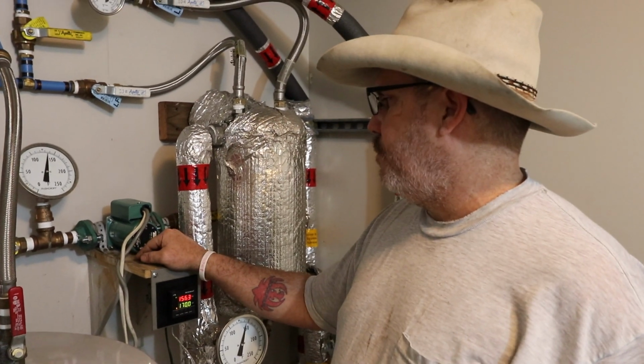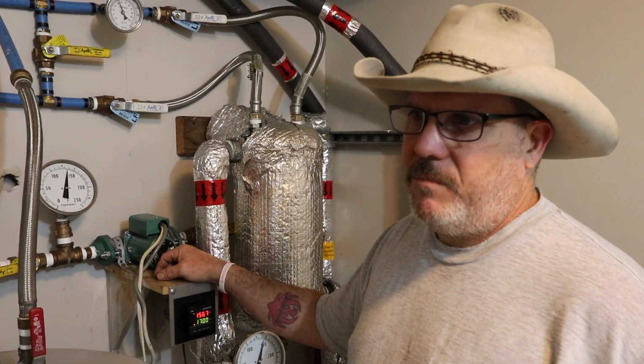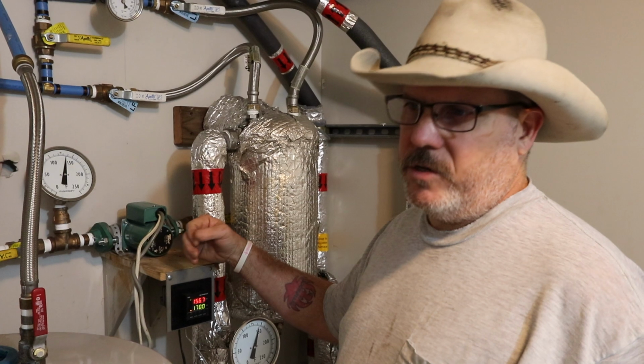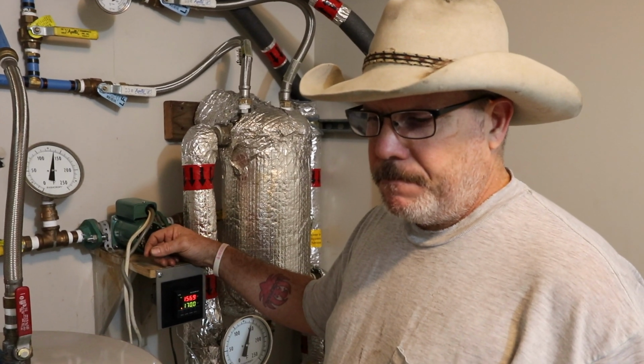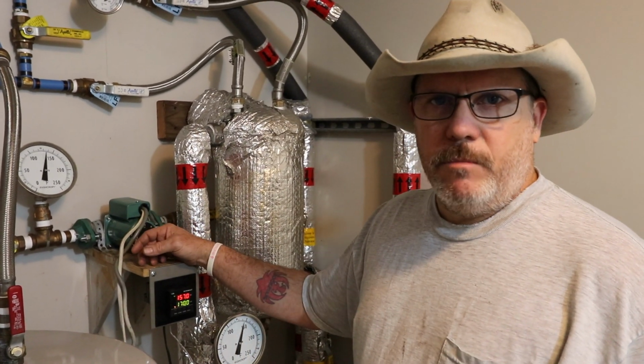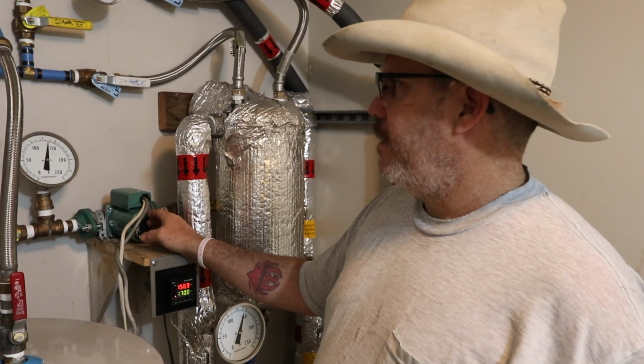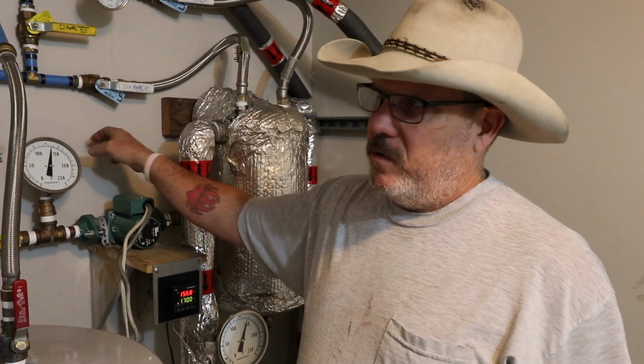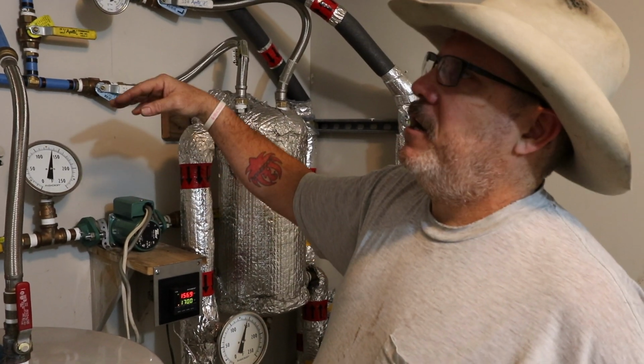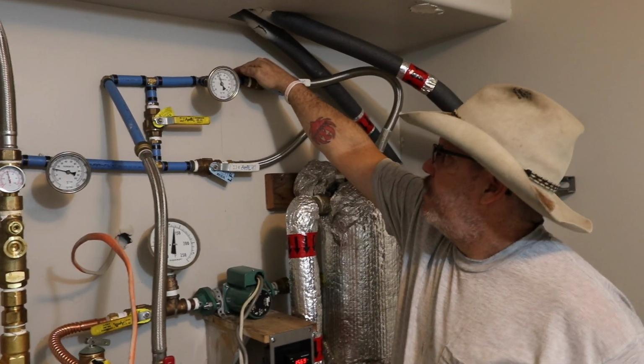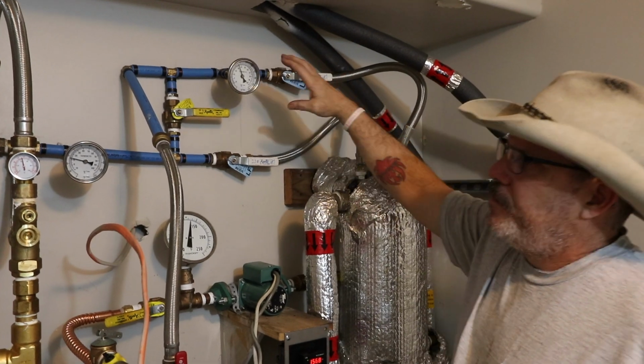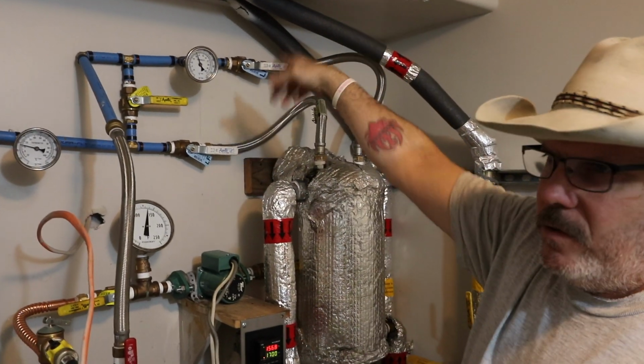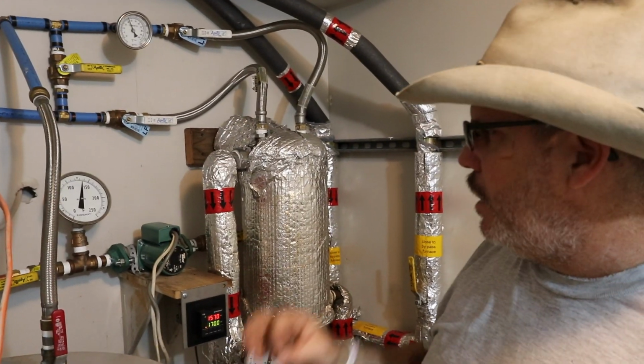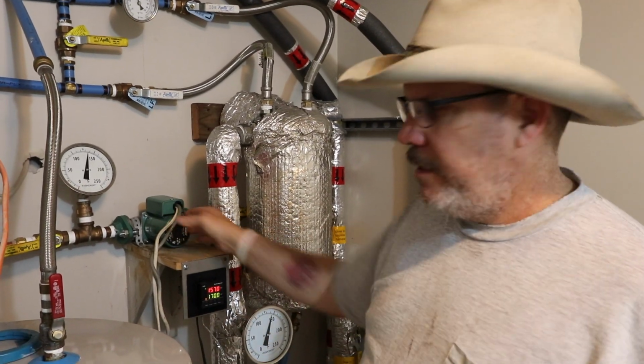But yeah, I use a Taco 007 SF5. They've got so many different pumps out there. You just got to know how big your loop is, what your head pressure is, how many gallons a minute you want to move. My boiler is not that far on the other side of this wall. We're in the basement right now. My ground level is probably about right through here. So my boiler is not that far from here, so I don't have a lot of head.